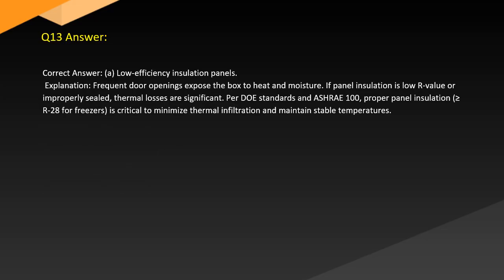Answer. Correct answer: A. Low-efficiency insulation panels. Explanation: frequent door openings expose the box to heat and moisture. If panel insulation is low R-value or improperly sealed, thermal losses are significant. Per DOE standards and ASHRAE 100, proper panel insulation equal to R-28 for freezers is critical to minimize thermal infiltration and maintain stable temperatures.